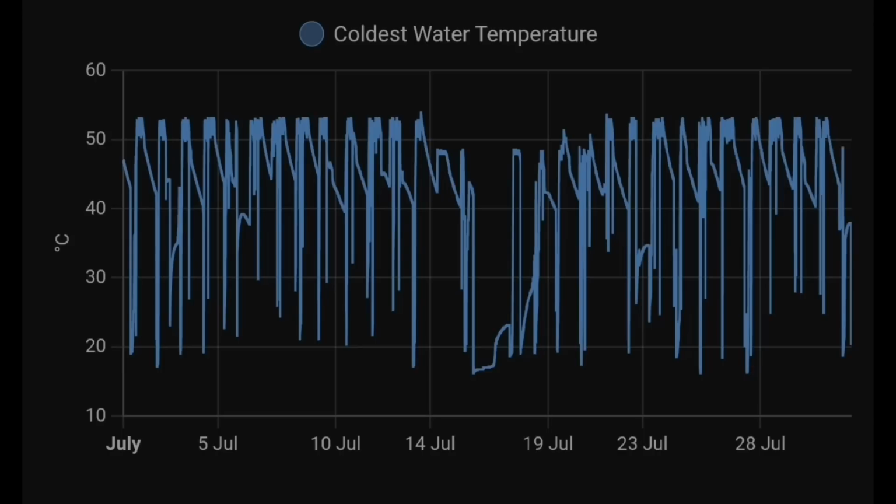And when I contacted Mixergy to find out, they confirmed that there had been a software change and they're trying to implement something where there is a differential between the cold water temperature and the hot water temperature. So they're trying to increase the differential and presumably make it an efficiency improvement. But that probably works well for people that are using the tank in the digital way, that are using the artificial intelligence that's provided by the Mixergy tank. But for those of us that are relying on the manual thermostat and using the third-party hot water diverter method that they provide, then it looks like it's causing a problem. So I had to report that, and they've backed the software out for me. So I'm back again filling up to 100% while they investigate what's gone on and how they can improve it.